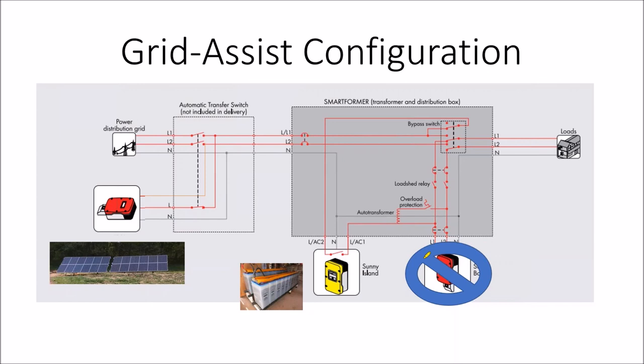Now, the grid assist configuration is used to kind of tell the utility that you're not interconnecting. So you might get an electrical permit, but not an interconnection agreement. That might flag it so the utility doesn't move you onto that punitive rate structure, since there's no interconnection agreement.